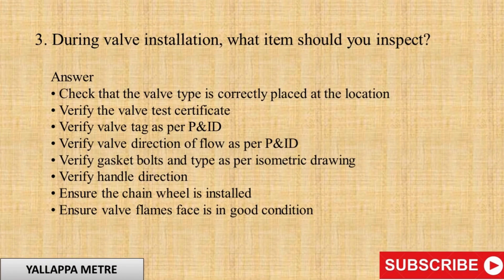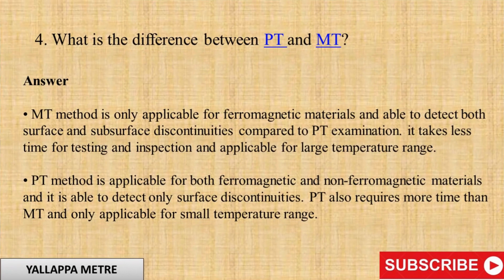Question 3: During valve installation, what items should you inspect? Answer: Check that the valve type is correctly placed at the location, verify the valve test certificate, verify valve tag as per P&ID, verify valve direction of flow as per P&ID, verify gasket bolts and type as per isometric drawing, verify handle direction, ensure the chain wheel is installed, ensure valve flange face is in good condition.